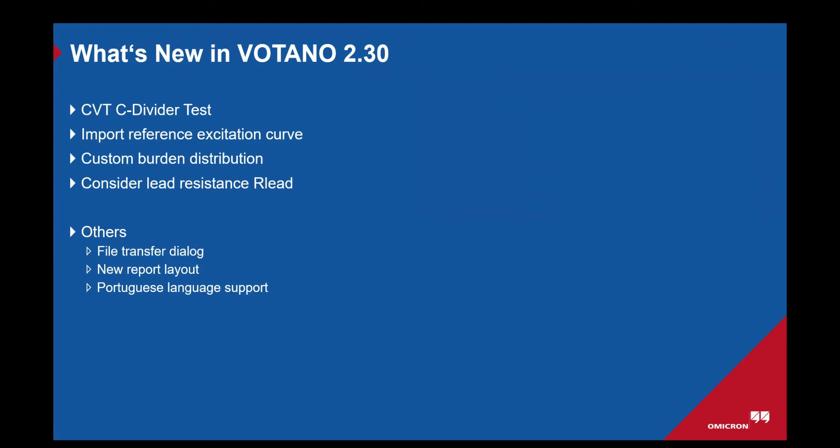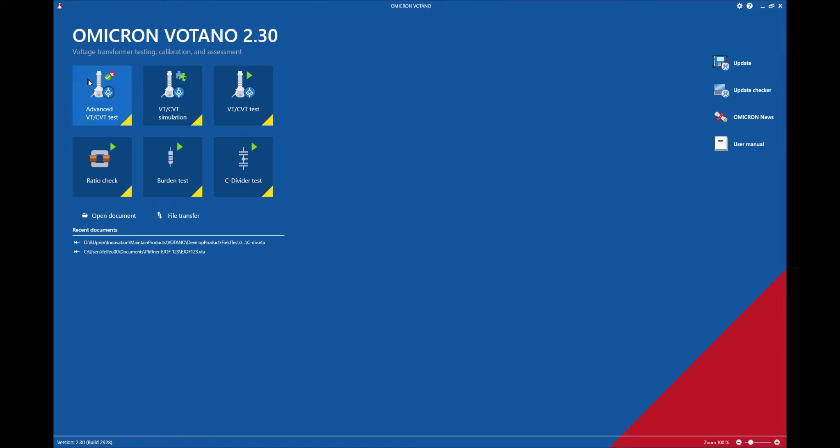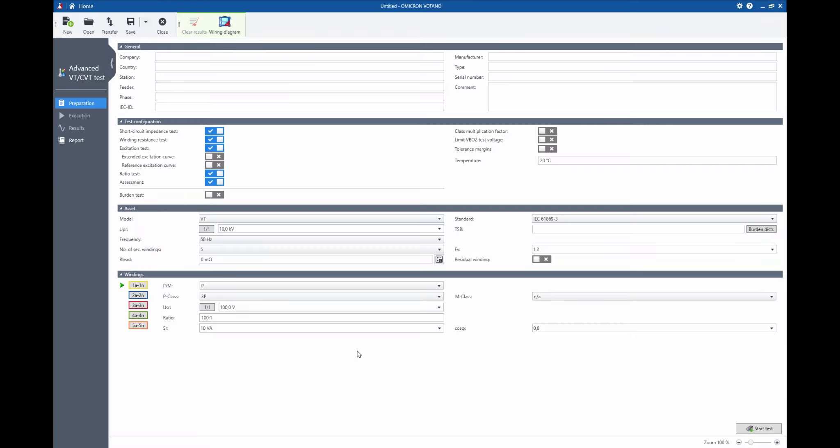The second feature on our list is the import reference excitation curve. This one is part of the advanced CVT test and it is here in the test configuration. If I activate it I can load a different Votano measurement, a previously done Votano measurement, and use this excitation curve instead of performing one in this test session.